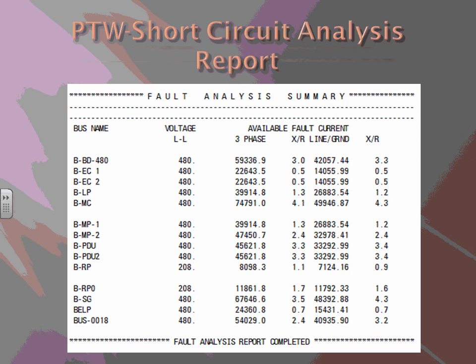Short circuit analysis on just the whole one-line diagram. Just showing, for instance, the 480 bus on the 3-phase, it will fault current at 59,336 amps, and single phase 42,057 amps.